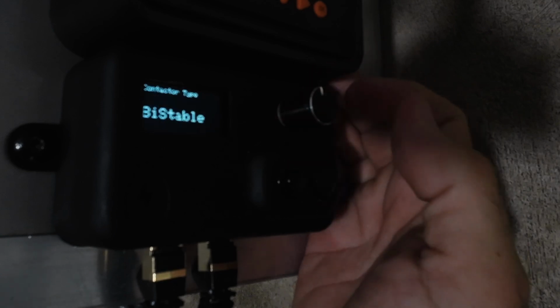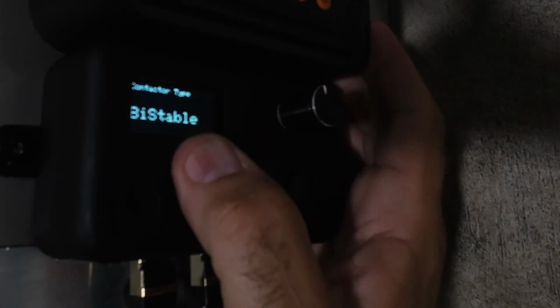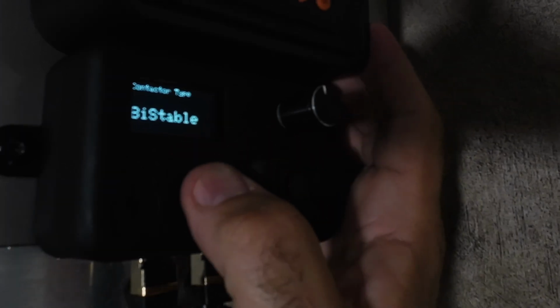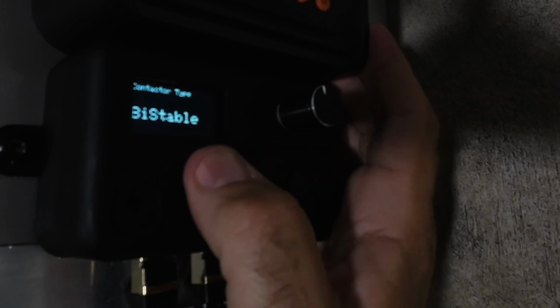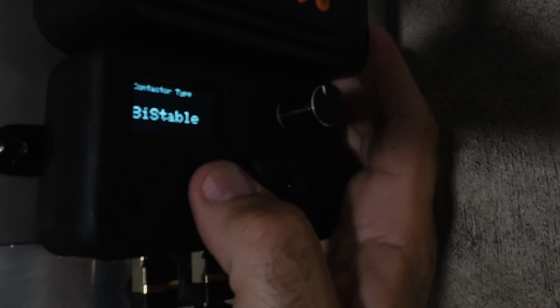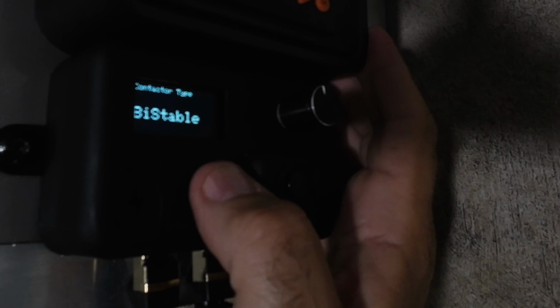Contactor type, bistable. I'm using a bistable contactor. There's also monostable. If you set it for monostable and connect it to a bistable contactor, it will destroy the contactor, so never do that.